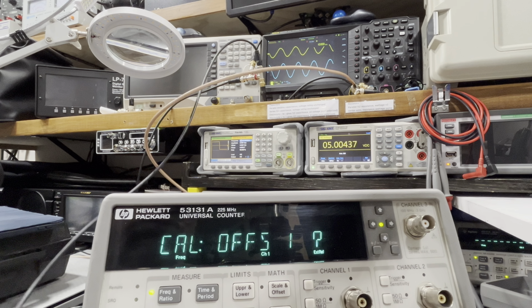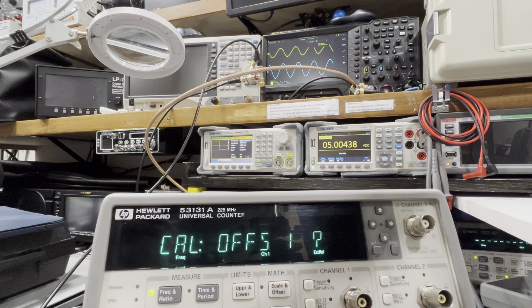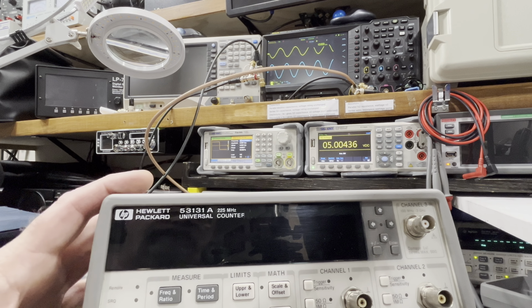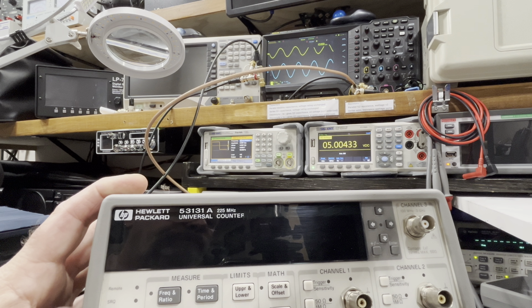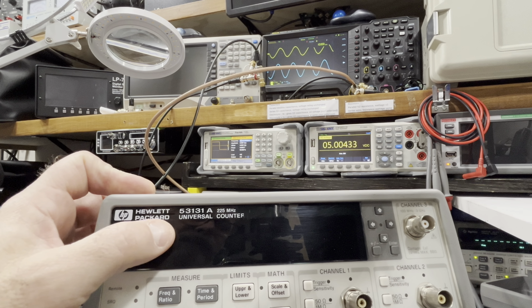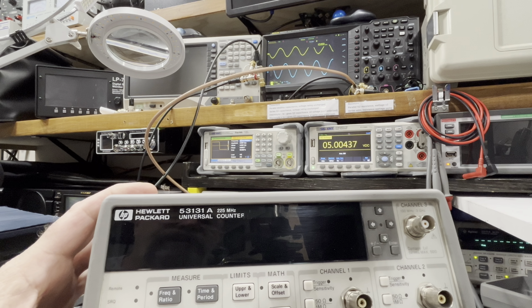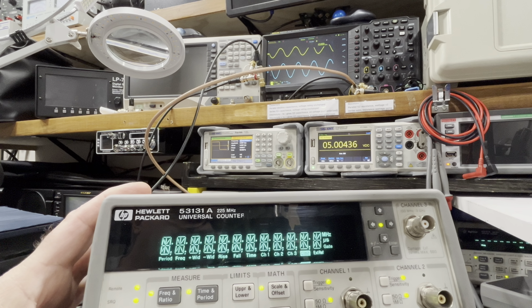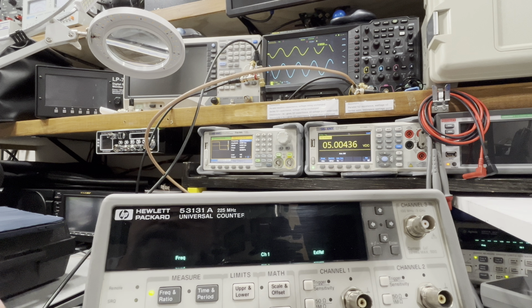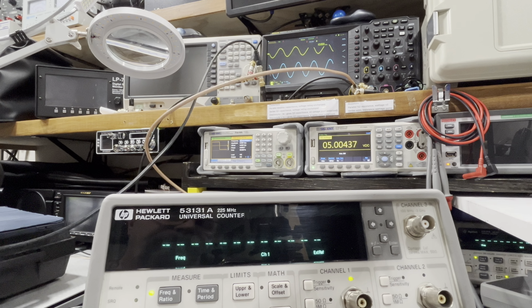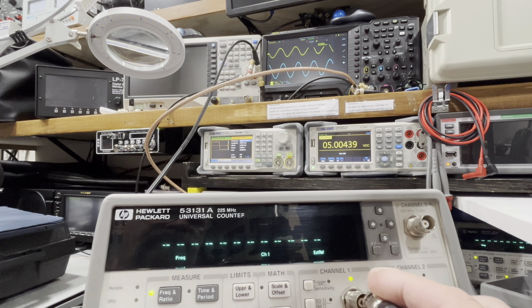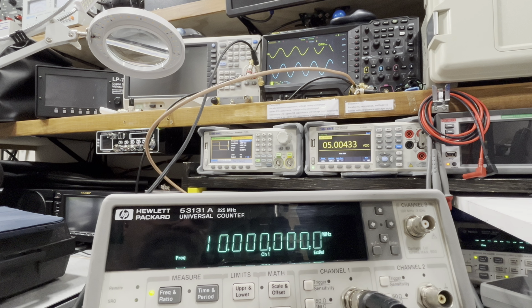Now we're done. Back to 0. We're going to turn it off. We can actually hit stop. Turn it off. We'll cycle it. Now, if it didn't do the calibration right, it's going to come up calibration needed. And there we are. So what I'm going to do is take our rubidium. We're going to put it in. It should be 10 megahertz.